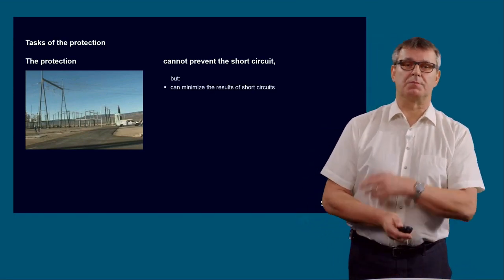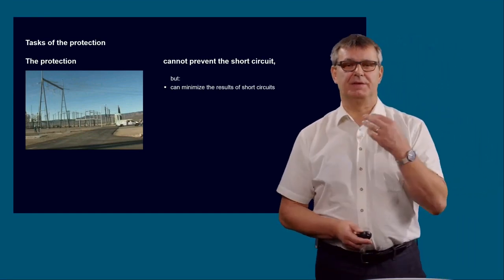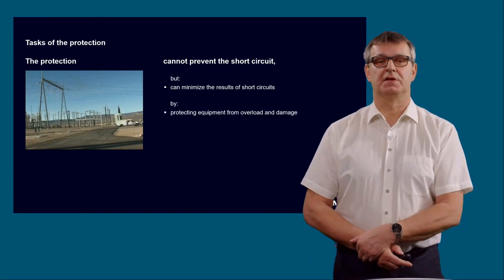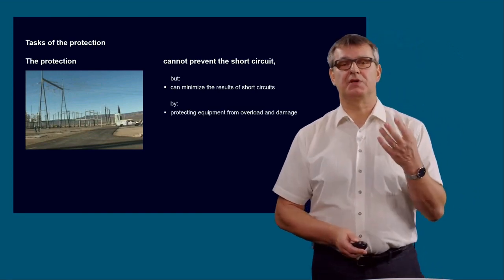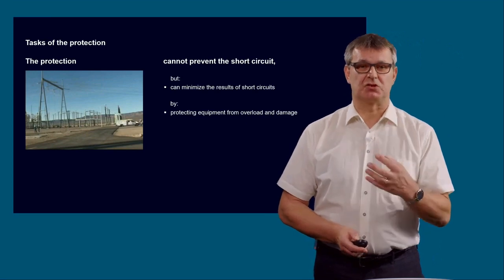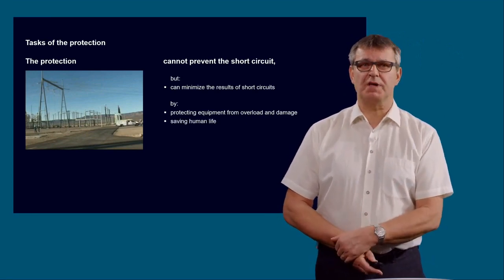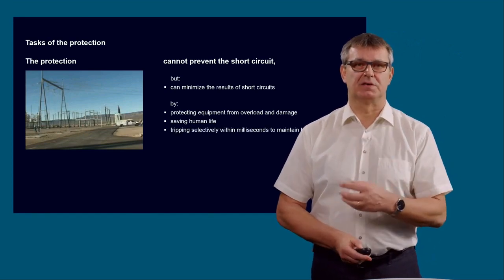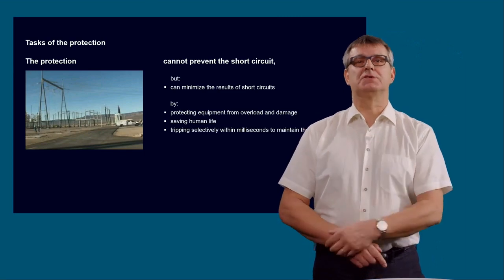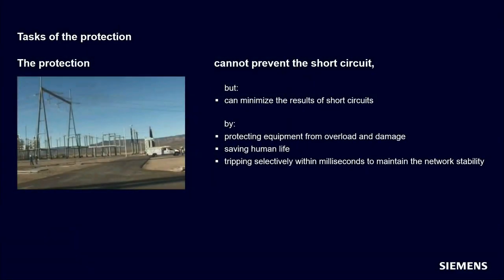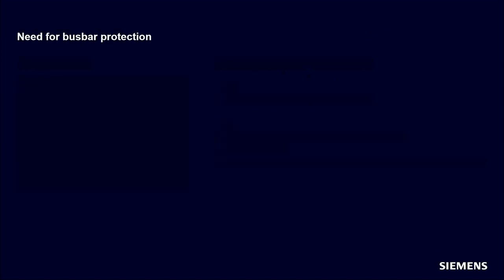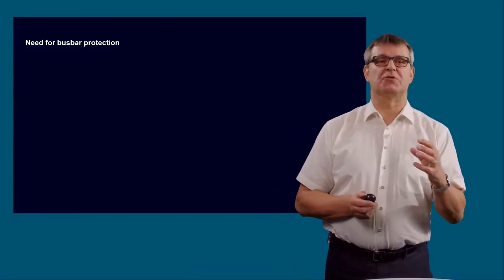So busbar protection cannot prevent the short circuit, but it can minimize the results of short circuits by protecting the equipment from overload and also from damage. And of course, very important, to save human life. And how does it do that? Protection protects human life and prevents damage to the equipment by tripping selectively within milliseconds, to also maintain the network stability.